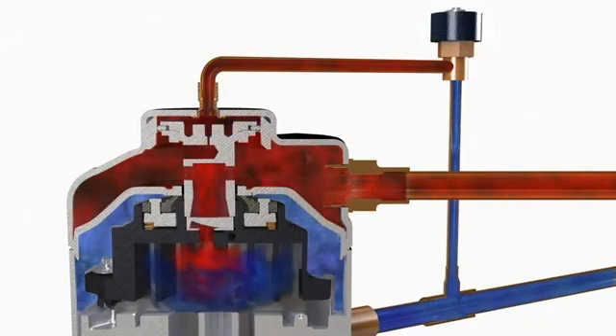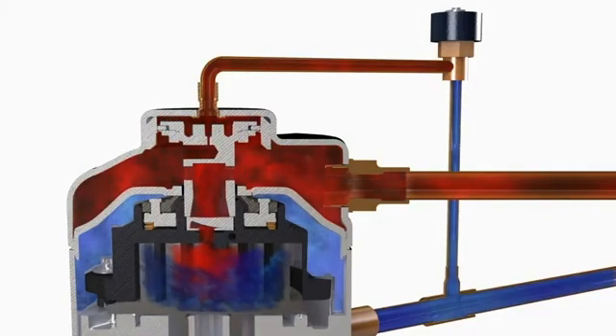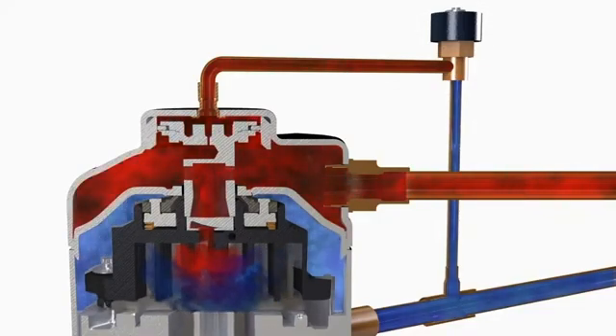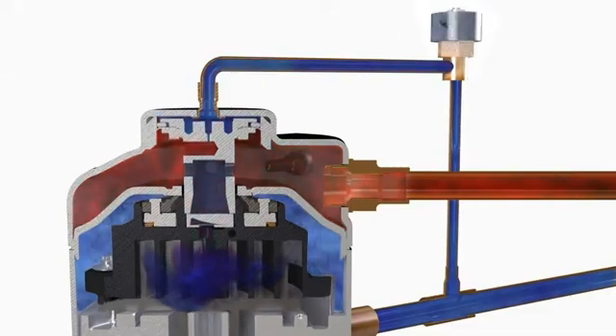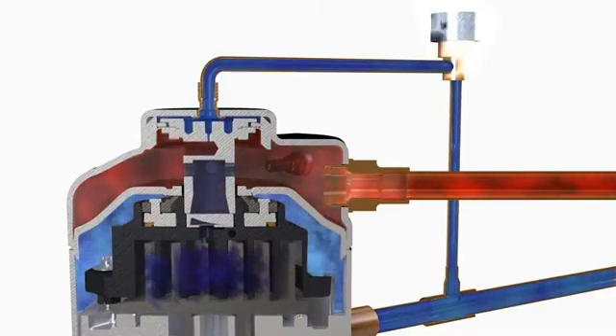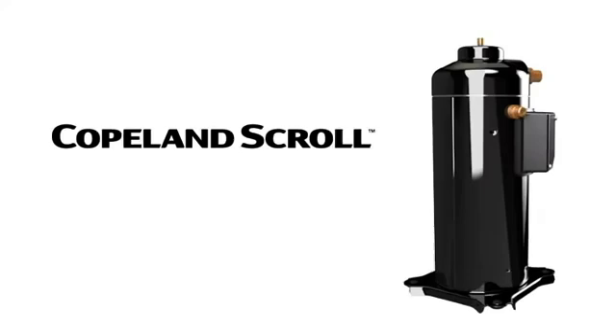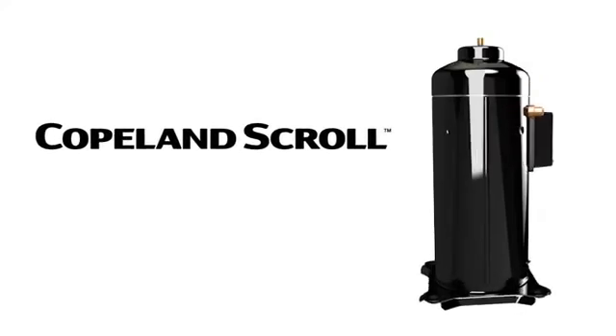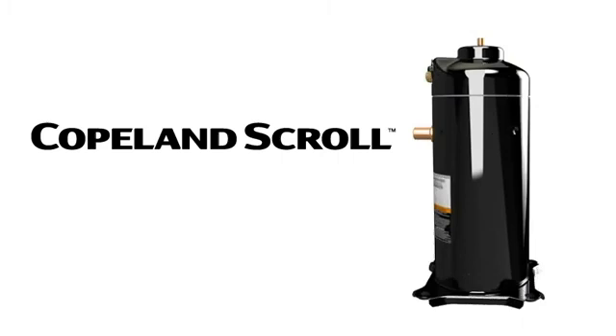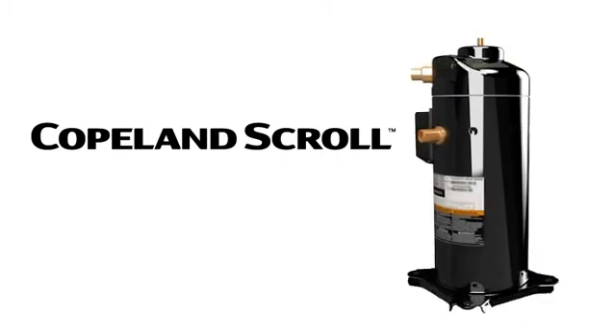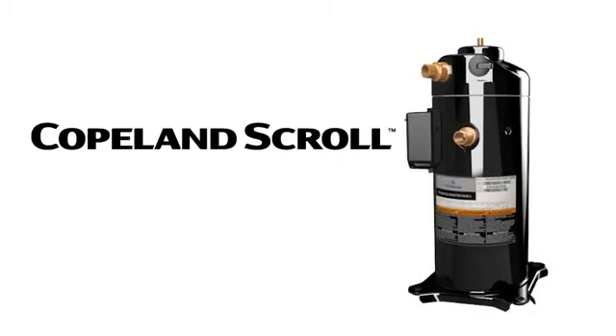This capacity control method lessens mechanical wear by reducing motor start-stop cycles and is up to 30% more efficient than other modulation methods such as hot gas bypass and suction throttling. The Copeland Scroll Compressor has earned its reputation as a leading solution for refrigeration systems by consistently and reliably protecting products from spoilage while delivering bottom-line savings.